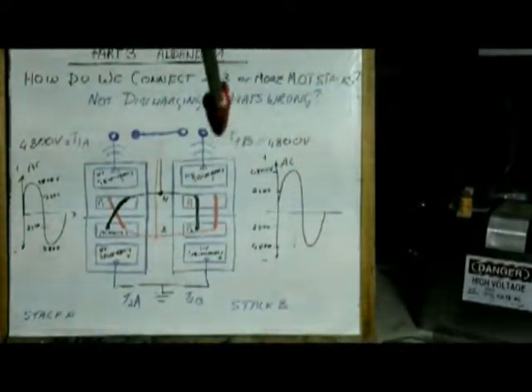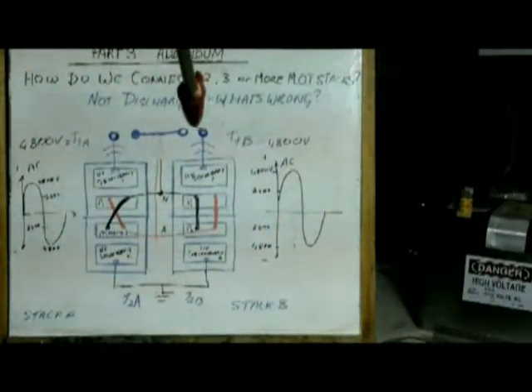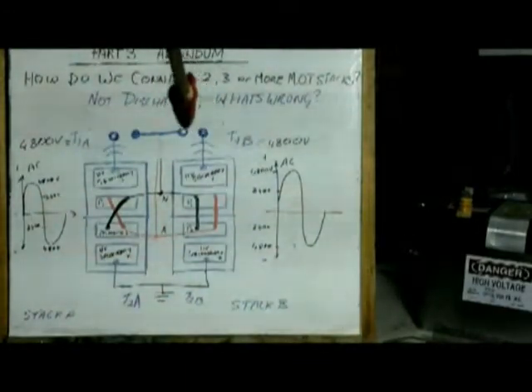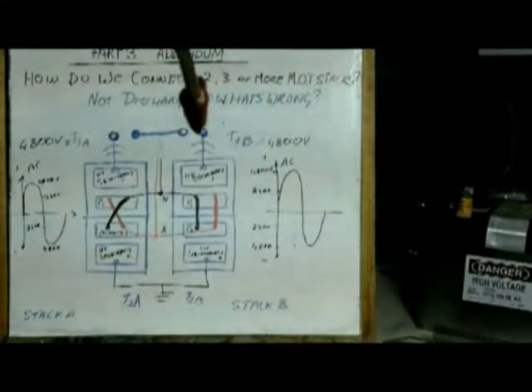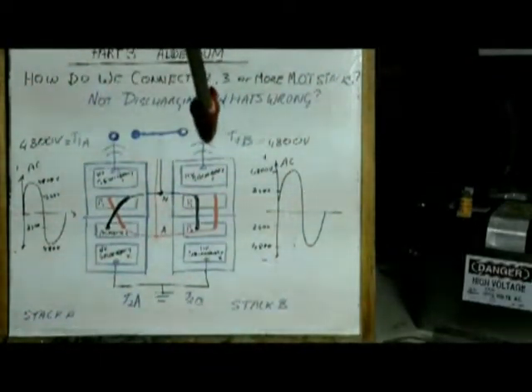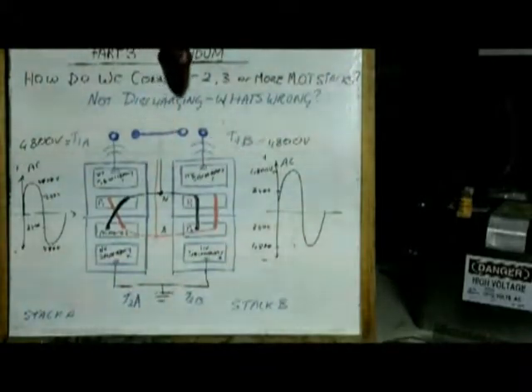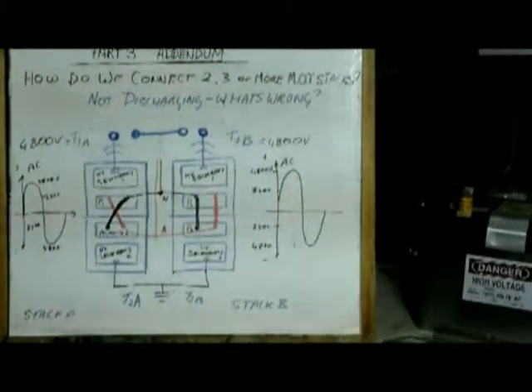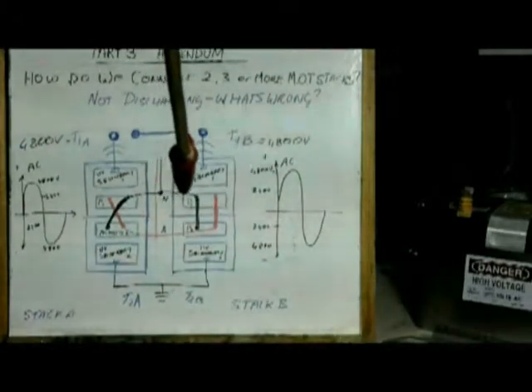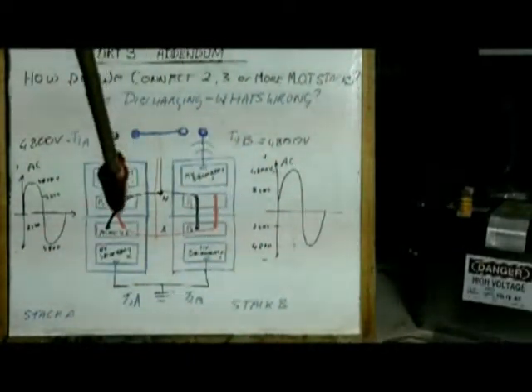So this arrangement can be useful. You'll have 4800 volts coming out of these terminals at twice the current. Okay, so it can be useful. But for our purposes, we want these to be out of phase, and we want a dual-ended transformer with a total of 9600 volts in this particular case. So what do we do? It's simple. We simply reverse one of the mains input to one of the stacks. We don't touch the hardwired connections anymore. It's only the input to one of the stacks. We can choose this one or this one. In this particular case, we'll choose this one.